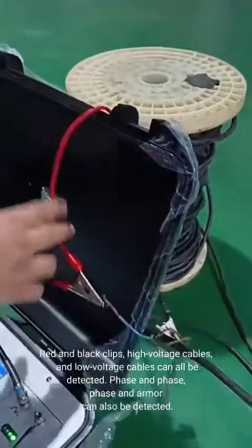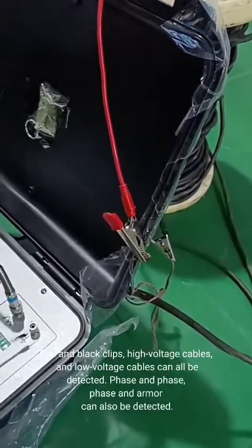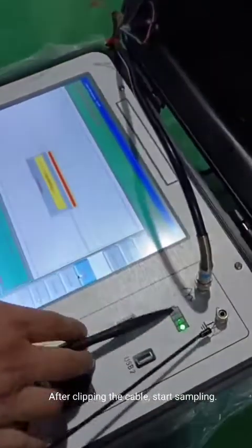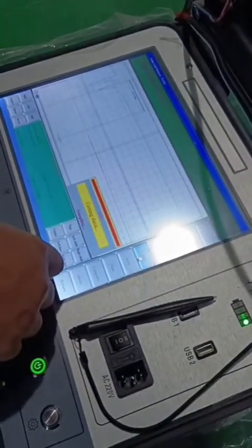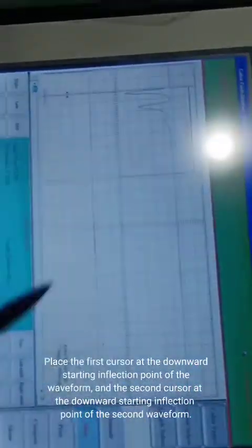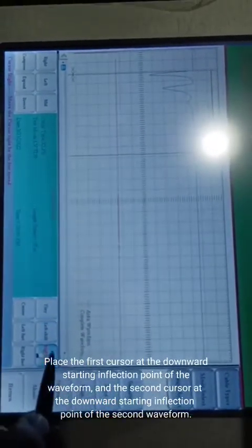Red and black clips, high voltage cables, and low voltage cables can all be detected — phase and phase, phase and armor can also be detected. After clipping the cable, start sampling. After the waveform comes out, adjust the waveform by the displacement and amplitude knob. Place the first cursor at the downward starting inflection point of the waveform, and the second cursor at the downward starting inflection point of the second waveform.